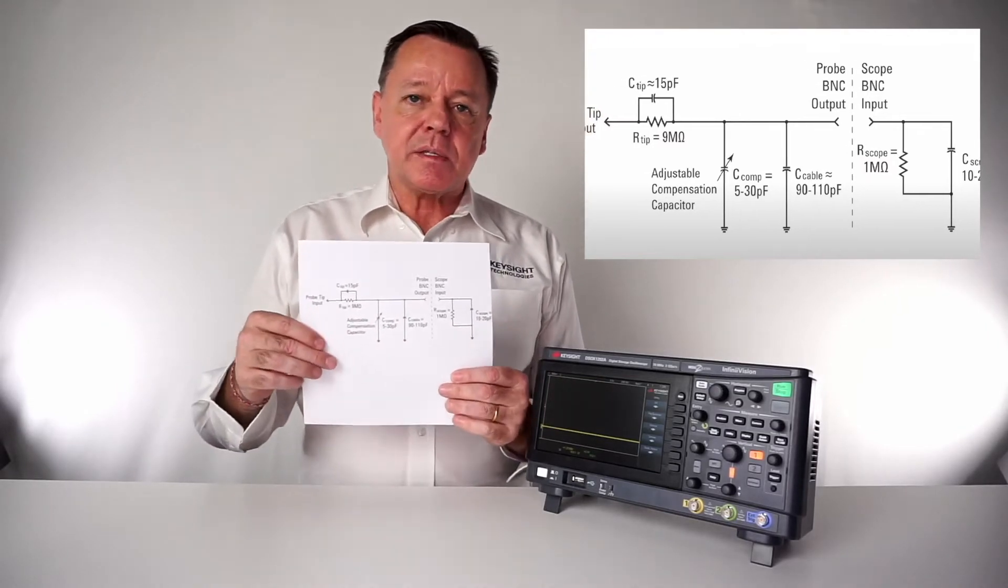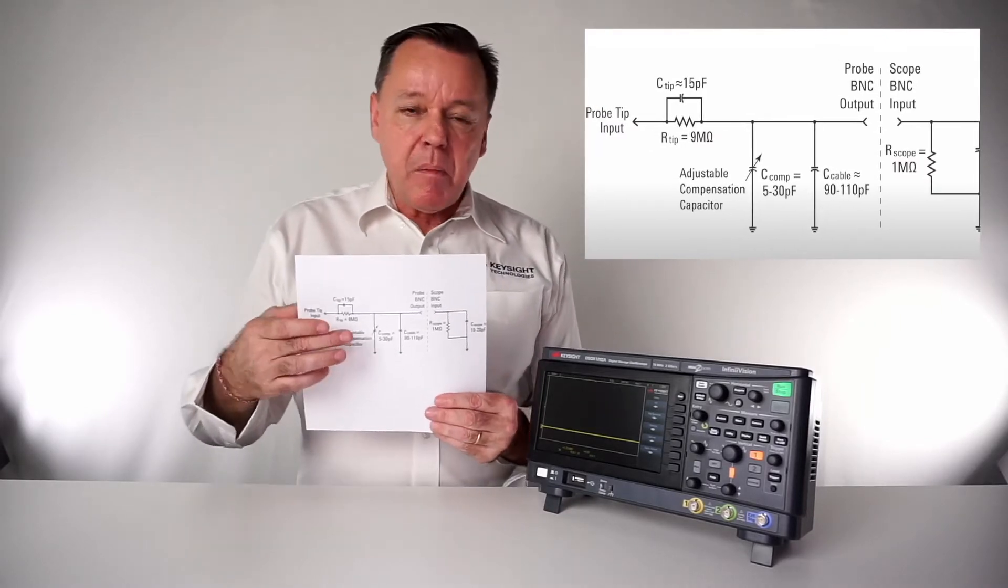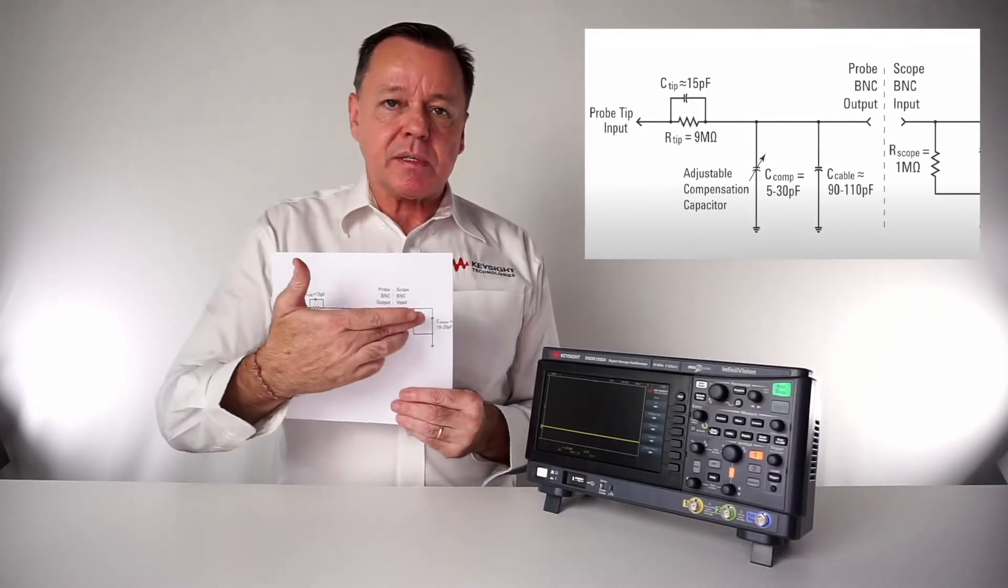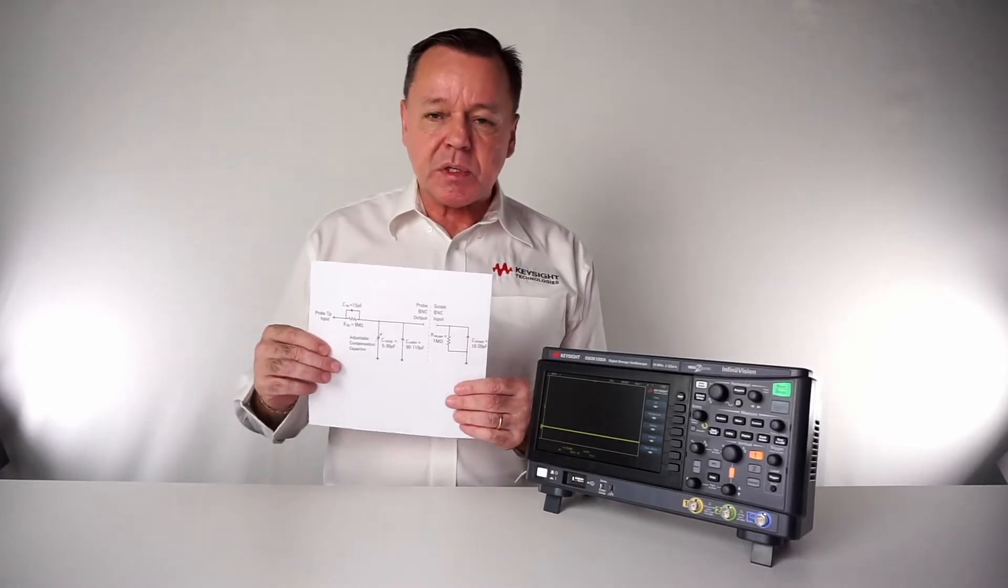The probe is designed not to have a lot of capacitance, but this has to be adjusted to be compatible with the oscilloscope input.